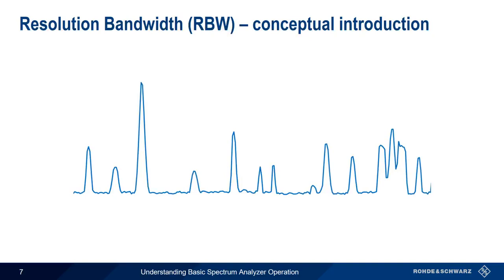One way to understand resolution bandwidth is to think of it as a window that moves across our span, measuring the level as it goes. This concept of a moving window can be helpful in understanding how swept spectrum analyzers work and what resolution bandwidth is.